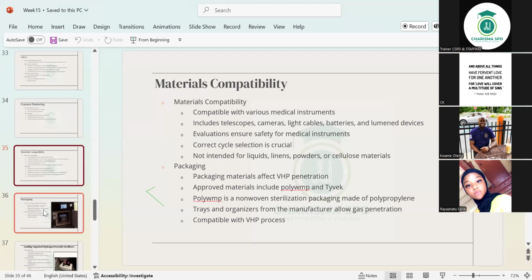Trays and organizers from the manufacturer allow gas penetration. So you should know that whatever tray you're using should allow gas penetration. If you don't understand the mechanism of that tray, the makeup of it, and you think that it's not the right thing, ask questions. They'll tell you why they're using it. Or maybe it's a mistake and they'll change it and give you one that will actually allow gas penetration. Okay? And whether the thing is compatible with the VHP process.